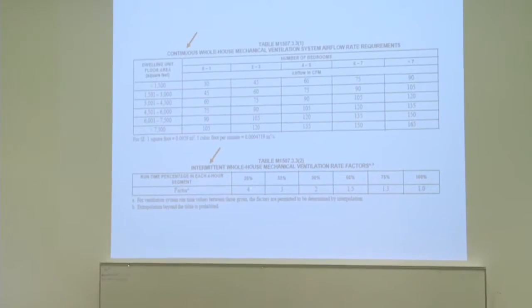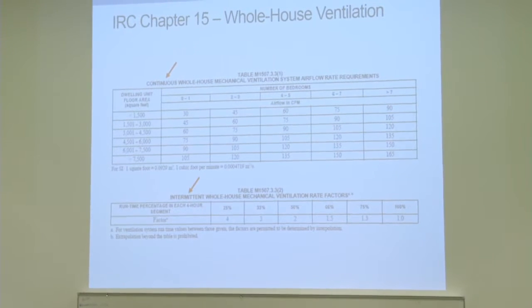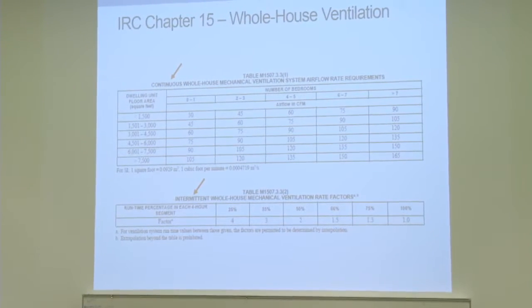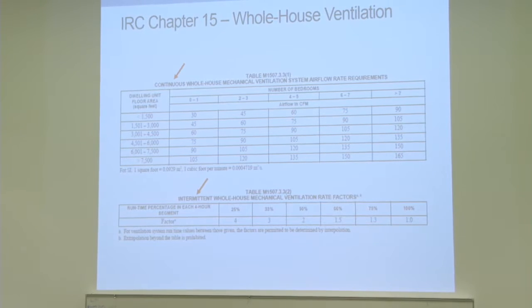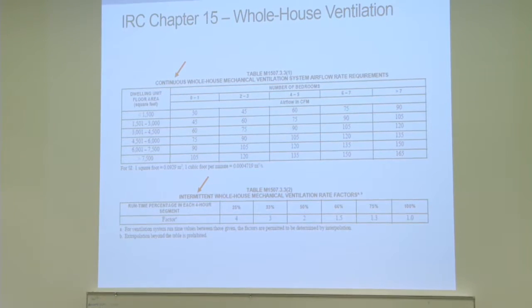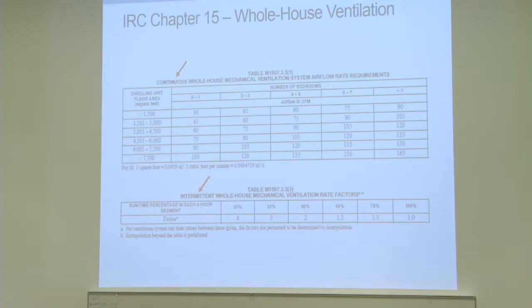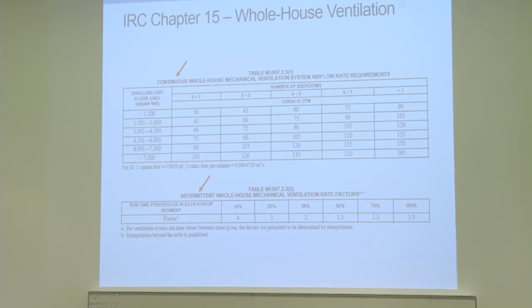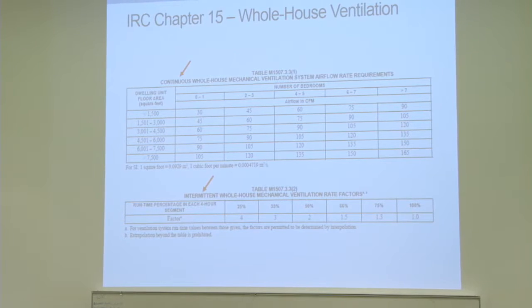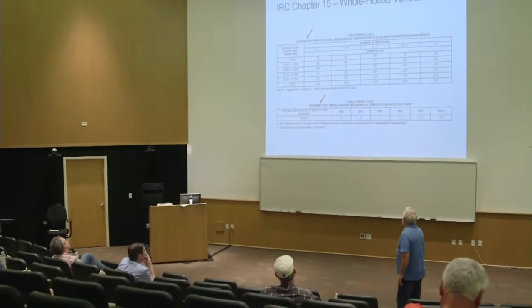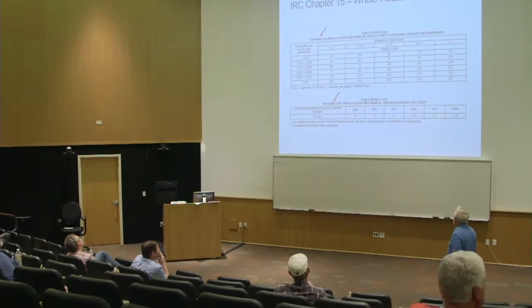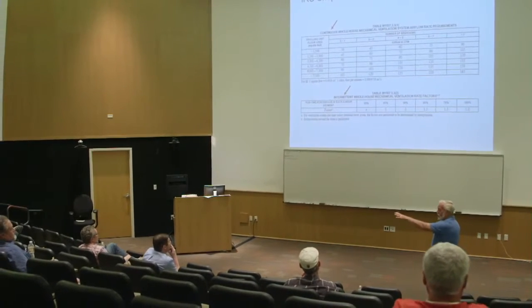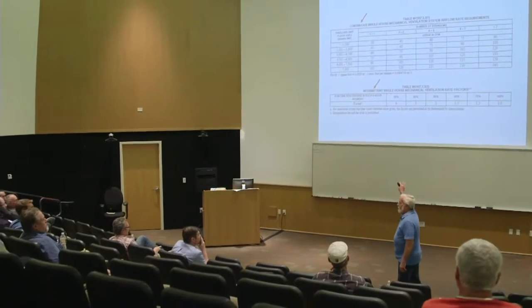If you only run it 25% of the time, or 1 hour every 4 hours, the fan has to be 4 times as big, doesn't it? If your requirement is for 30 CFM, but you only want to do it 1 hour every 4 hours, then you need to move 120 CFM for that 1 hour. And the code does say we don't want to go longer than 4 hours without doing some ventilation. So that's the lowest, 25% of the time, or 1 hour every 4 hours. So the numbers aren't real big. And these guys and the other manufacturers have fans that you can basically set close to those CFMs, right?